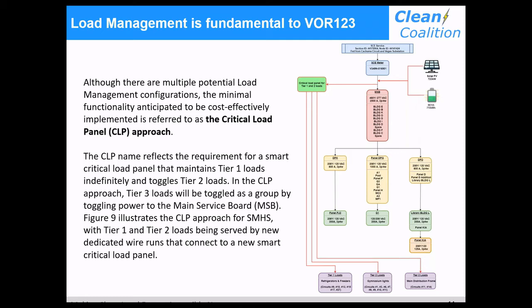What this basically allows you to do is serve your tier 1 and tier 2 loads directly off that critical load panel, which will automatically toggle the tier 2 loads off if needed to maintain the tier 1s, and toggle them back on once there's enough solar and/or energy storage state of charge. The tier 1s will be kept on forever - they never turn off.